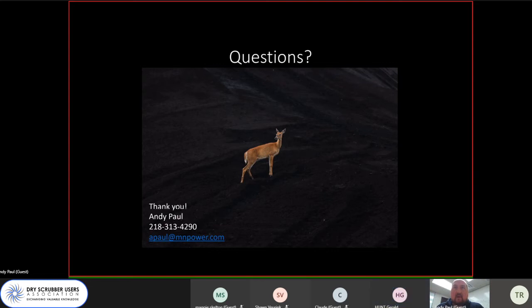We've worked really hard to make sure we're trying to keep a balance. We aren't able to optimize or fully use all of the Unit 4 water at the same time. We do lean pretty heavily on either pond 3 water or bottom ash water. They just have less pluggage problems with those two. So we have a set amount of Unit 4 water that we'll use, and then we fill the rest of the process water demand with pond 3 water and bottom ash return, just because they're a little cleaner.